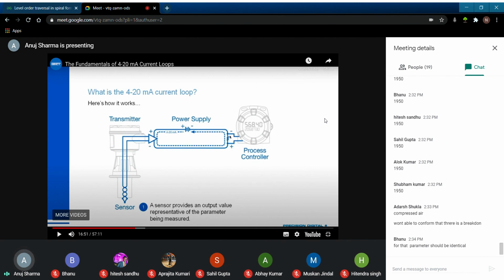So earlier what I was talking about was comparative value. That comparative value is always going to be same throughout a loop. For a particular instance, that value is going to be same. The value of current is going to change with the change of property of the sensor, but that comparison will not be changed and will not drop among the circuit, whether it is for longer wire or shorter wire, it will not matter. That is the reason that we use this 4 to 20 milliamp circuit. So let us continue with this.